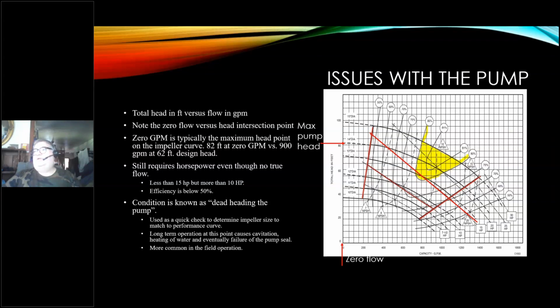Long-term operation at this point causes cavitation. It heats the water up and eventually fails the pump seal. It will make the water so hot that it starts leaking at the shaft. It's more common in the field than you know, and this is something that we're going to talk about later on, about a real-world condition where we run into this a lot, and you'll be surprised why. Okay, again, don't operate in that area.